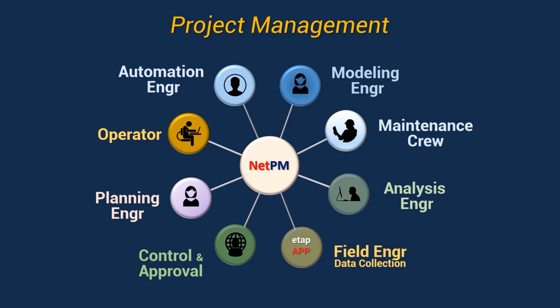So you could have an owner-operator host the master ETAP model and then assign different engineers a scope of work, as well as allowing outside consultants or contractors to take control of modeling a section of the system. They would then in turn check in the results, and the owner-operator or the designated administrator would review those changes and either approve, reject, or comment on the changes. All of this simultaneously running analysis and generating reports, all while keeping a single centralized database model.